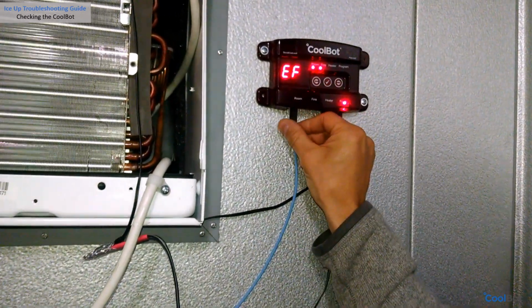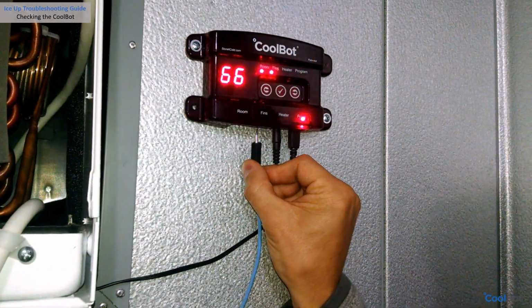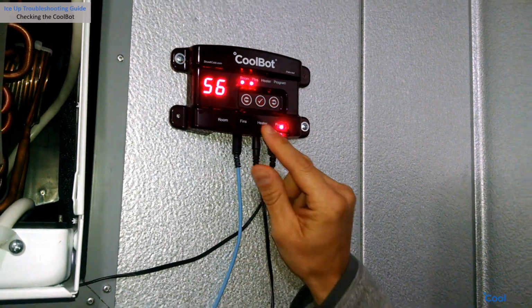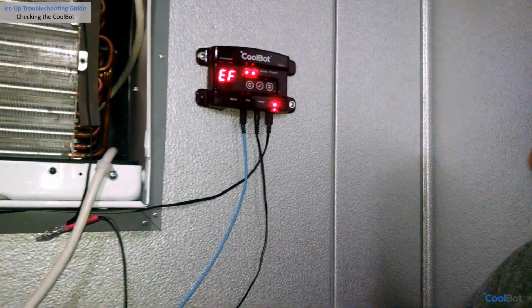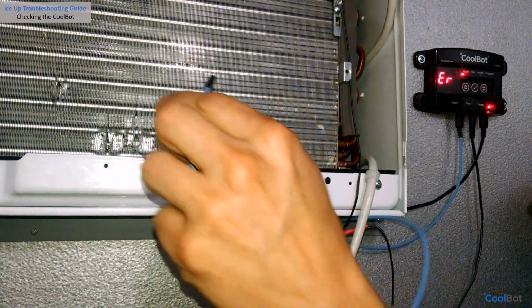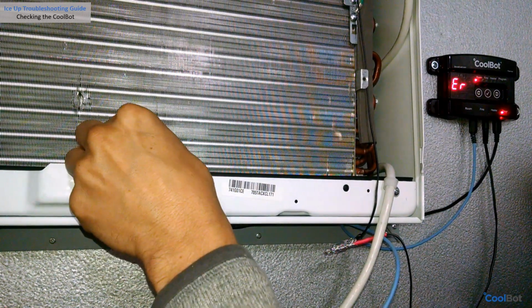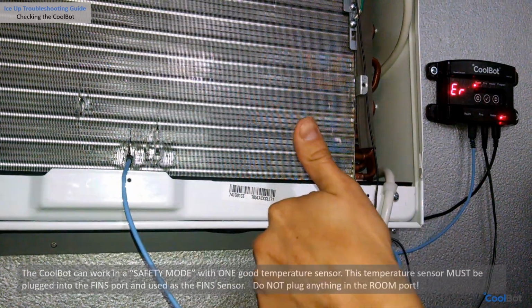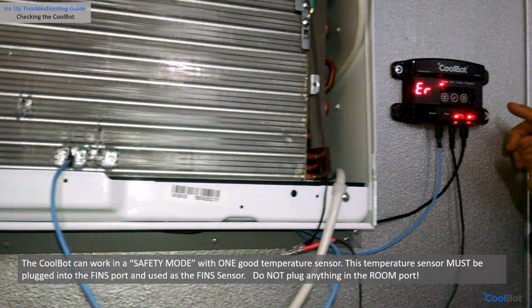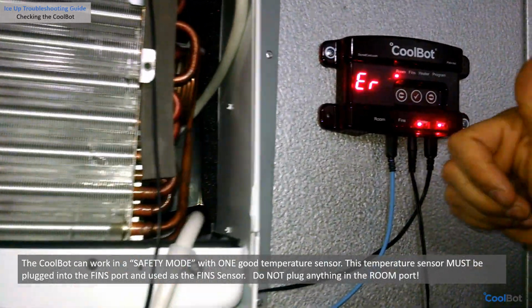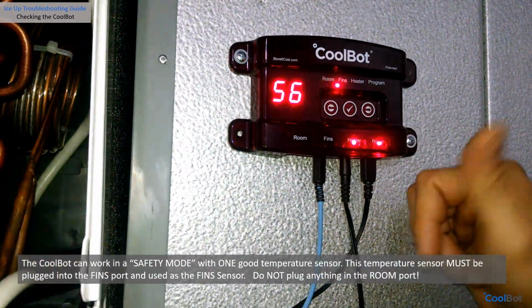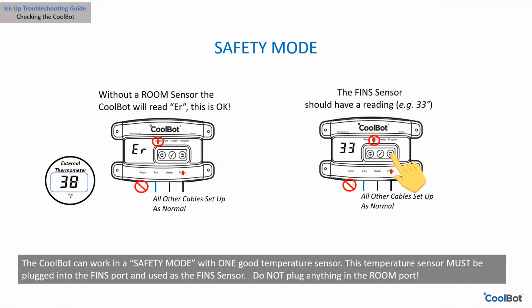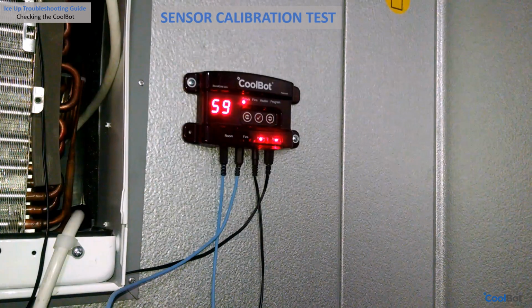Grab your room sensor and use it as your fin sensor. Make sure you plug it firmly into the fins port and the tip of the sensor is correctly positioned on the fins of the air conditioner, just like the other sensor was. Leave the CoolBot without a sensor plugged into the room port. An ER message will display permanently until a new sensor is installed in the room port. This is okay. Your CoolBot will be working on a safety mode in the meantime.